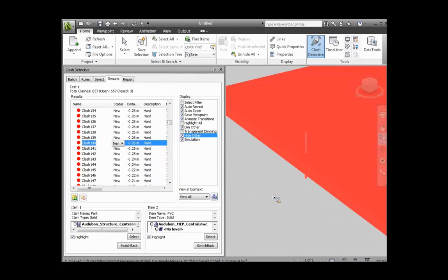What we typically do, in a big BIM cave meeting, or as a BIM coordinator prepping things for the BIM cave meeting, is go through and filter these and see if we can get that down to a valid number of clashes that actually need several different consultants to look at and resolve. And we can start to classify those clashes. We can say that clash is active, it's been reviewed, it's been approved, it's been resolved.